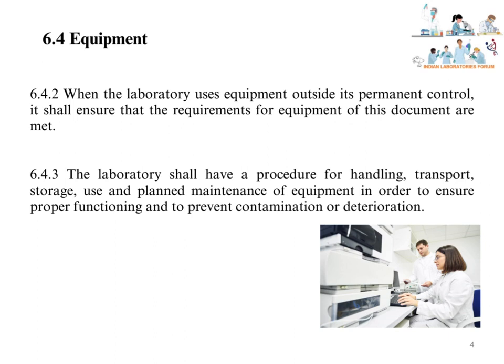The laboratory shall have a procedure for handling, transport, storage, use, and planned maintenance of equipment in order to ensure proper functioning and to prevent contamination or deterioration. This clause demands a procedure detailing handling, transportation, storage, use, and maintenance of equipment, including operation, calibration, and maintenance.